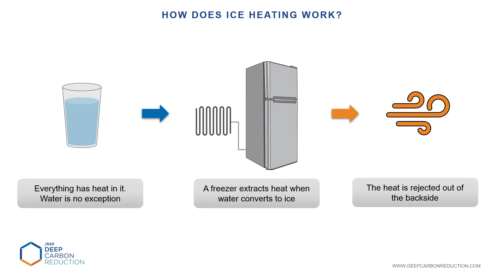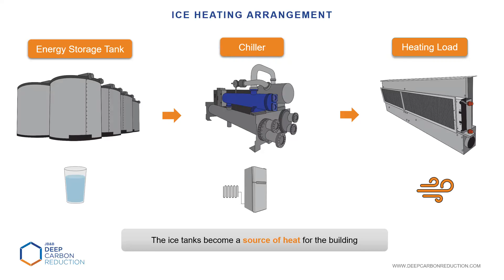If we scale this analogy to equipment we're familiar with in the commercial HVAC industry, it looks something like this — our ice heating arrangement, where we start with the ice tank, which is actually just a big tank of water. That's how it usually starts. If we apply an ice chiller or a glycol chiller that makes ice, we pull that heat out. In traditional cooling systems, that heat is usually thrown out through a cooling tower — there's some associated mechanism to dissipate that heat. In this arrangement, we are not going to throw that heat out. We are going to distribute that water, usually through a hydronic system, to a heating load inside the actual building.